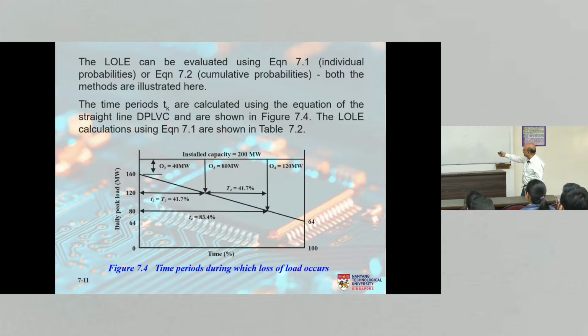I'm not able to supply the load for this small time T3. So you can calculate this time using y is equal to mx plus c, yeah? And you will find that it is 41.7% in terms of percentage. Okay, so then the next outage will be 120 megawatt, and then you can find this small T4, yeah? Again, using the equation of the line. So actually we have all the T's and we have all the P's, and all we need to do is now PK times TK, and then add them all up and you'll get the risk in the system.